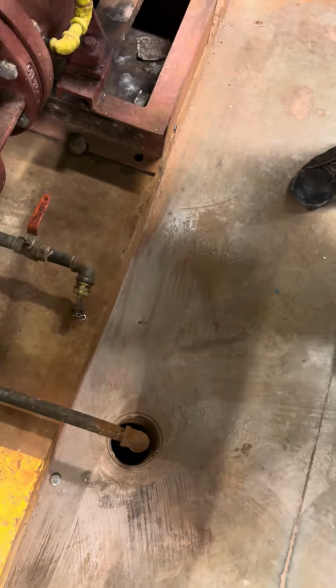So, as you can see, the thing there is like water. Up the top, at the back there, you can't really see it, but there's a pneumatic control valve up there that's controlling the steam that we're supplying into this heat exchanger right here. This pump is then supplying the water throughout the entire building, brings it back in and keeps it warm. So we have two things to keep an eye on. One is obviously the pressure. We can make sure the pressure is up to par. So we come in every day and look at the pressure. Pressure can be anywhere from 50 to 60, just based on how big your building is. The rule of thumb is 7 to 10 psi per floor, which is 5 floors, so we've got about 50 psi.